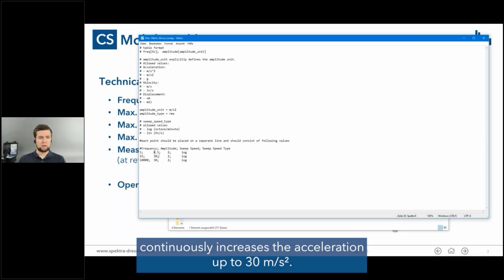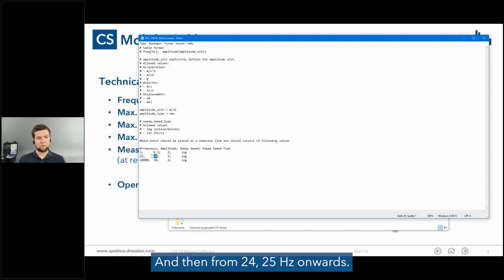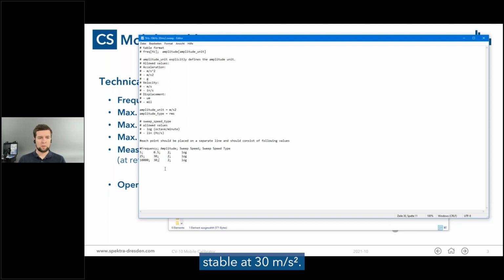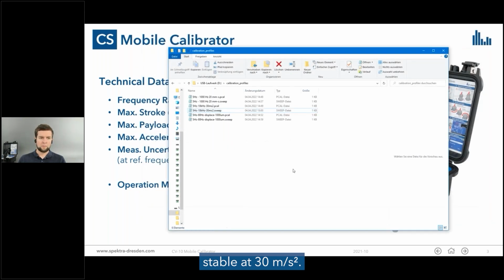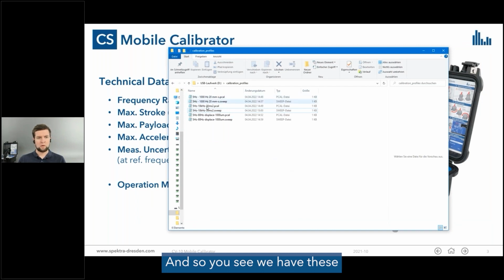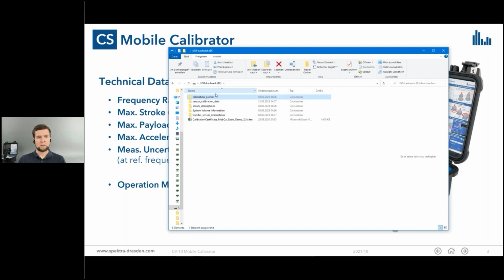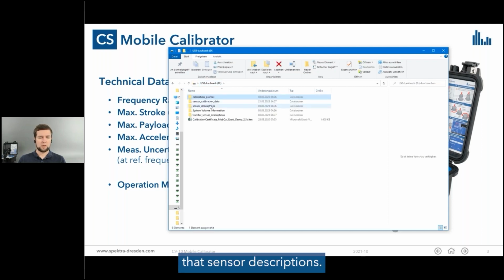Continuously increases the acceleration up to 30 meters per second square, and then from 25 hertz onwards, it keeps the amplitude stable at 30 meters per second square. Okay, so you see we have these different calibration profiles. And next step will be the sensor descriptions.